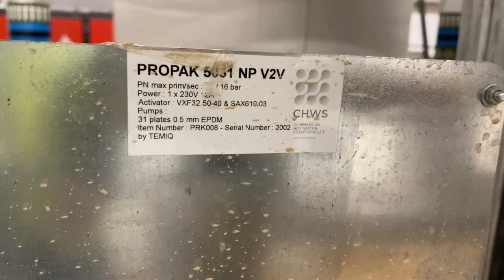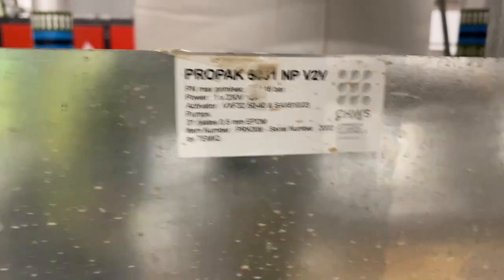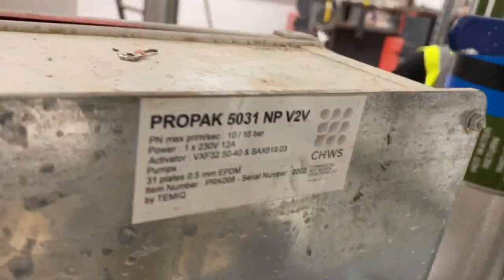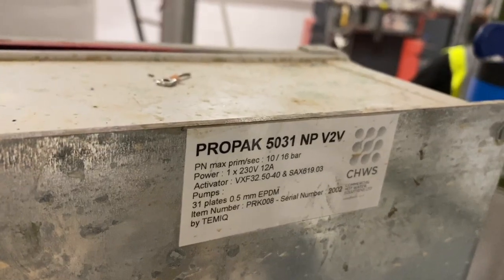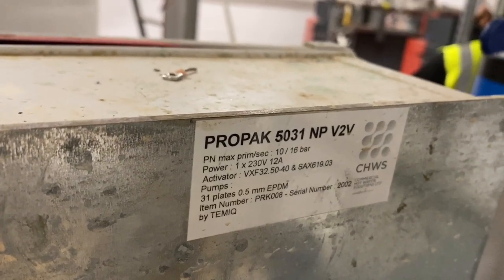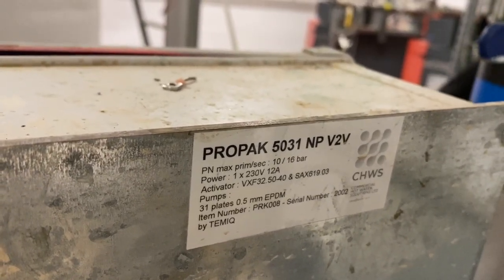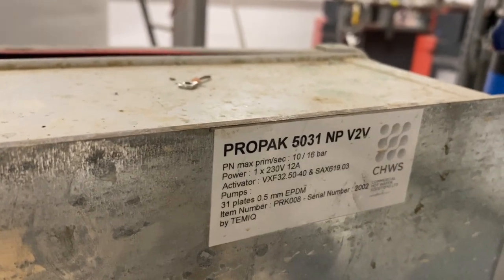And every unit has the model number and device. So NP no pump, I believe. V2V. 2-port valve. So we take all this information down on our commissioning form. These units are rated to PN 16 bar. Normally you can get ones, the more stock item is lower rating to about 10, I believe.